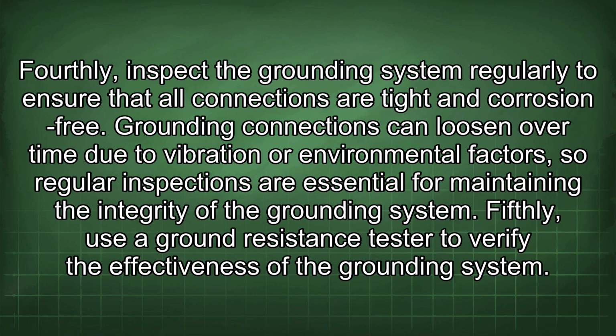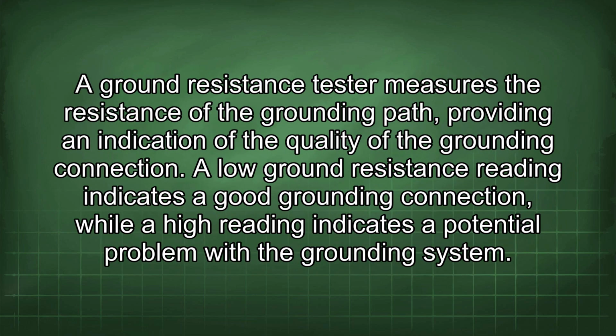Grounding connections can loosen over time due to vibration or environmental factors, so regular inspections are essential for maintaining the integrity of the grounding system. Fifthly, use a ground resistance tester to verify the effectiveness of the grounding system. A ground resistance tester measures the resistance of the grounding path, providing an indication of the quality of the grounding connection.